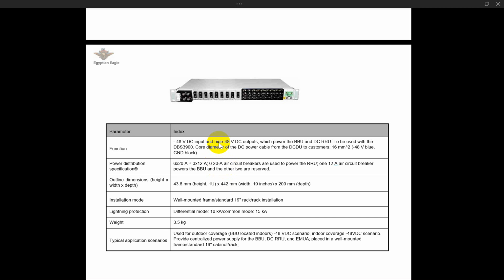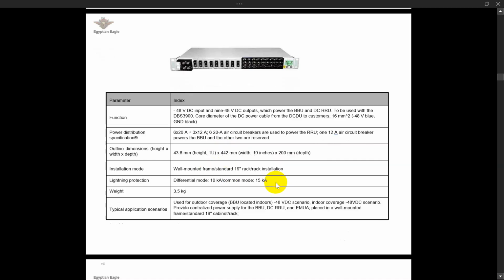One more thing for this DCDU: if we are going to load it with RRU, RFU or other big loads, we should connect to a high-rated breaker inside the rectifier so it can cover the load of the equipment. And for this we can give the power as usual for RRU, AMU or BBU, according to the scenario approved by the operator of the scope.